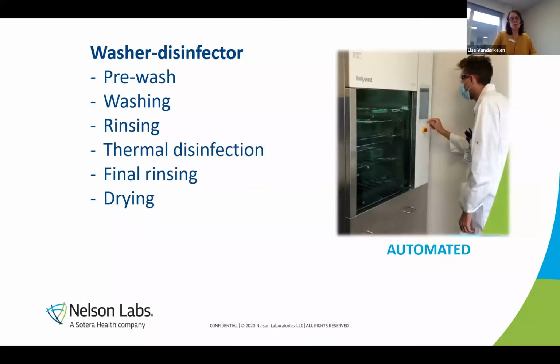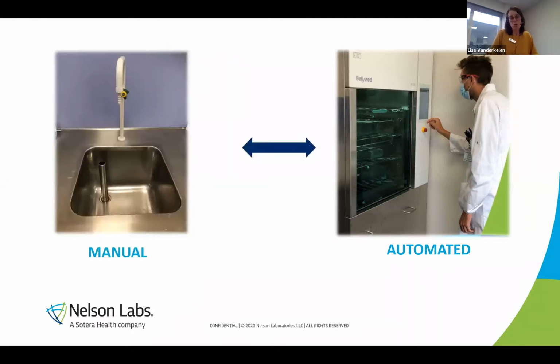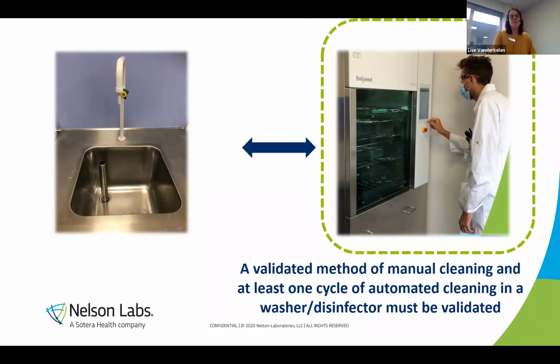Or you can use an automated cleaning step, which is using a washer disinfector. Here, each step of your wash cycle should be clearly defined, how long it should take, at which temperature, how much detergent you're going to use, and you generally have a pre-wash, a washing, a rinsing, a thermal disinfection, and a final rinsing and a dry time step. So it's clear that you can choose between two generally accepted ways of cleaning. If your device can be cleaned with a washer disinfector, you should validate a procedure with an automated cleaning.